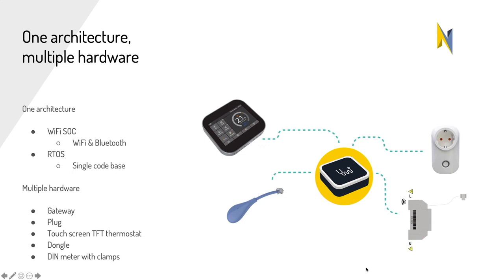You just click the clamp around the mains stream. We have a single phase and a three phase version. And the voltage we measure through the power supply, which are just a line and a neutral connection. So it's a very easy to install product, but it does give us much more richness in data. Since you're in the metering cabinet, you're always within Wi-Fi range. Installation, again, very easy via Bluetooth. And we're measuring voltage, we're measuring current, we're measuring real power, active power, reactive power, and we can oversample and get much more granularity than just the 1 second data out of the product.